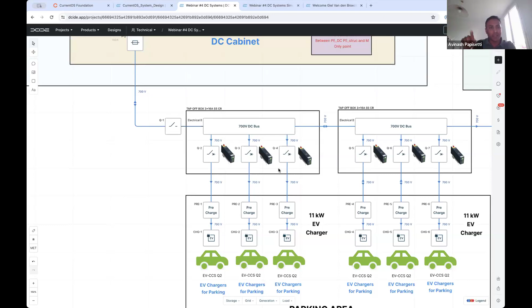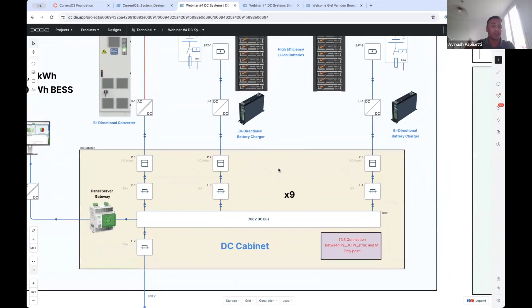In the same way, the 9 battery chargers—9 strings of energy storage in parallel—do not communicate with each other. They work as standalone units and don't care what the others are doing. If the voltage is 700, a unit is on standby. If it's 710 volts, it should charge the batteries. If it's 690 volts, it should discharge the batteries. The same philosophy is followed by everyone, and they act independently.